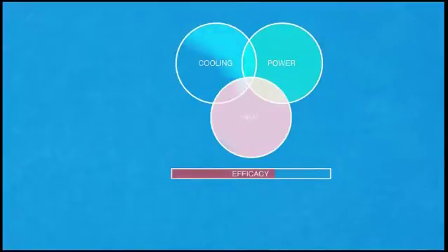However, there are going to be times when heat is not required, particularly in hotter countries. One answer is tri-generation, or poly-generation. This third output is district cooling. The power station uses heat to power absorption chillers, as opposed to the compressor refrigeration process used in most air conditioning units and refrigerators.